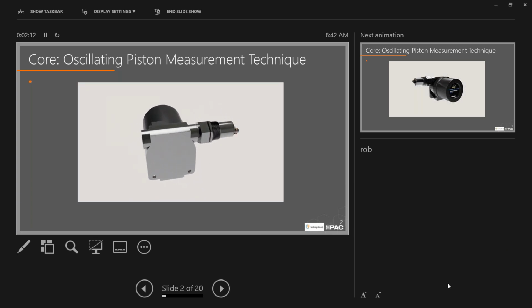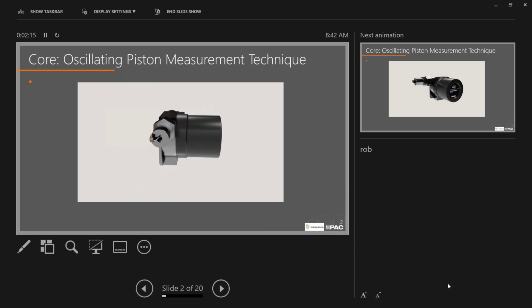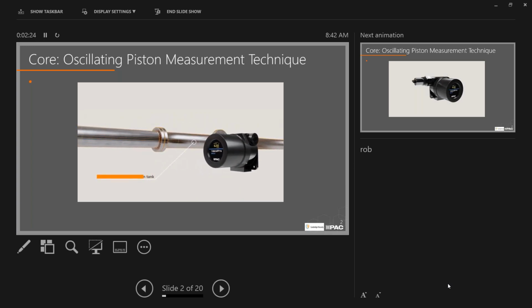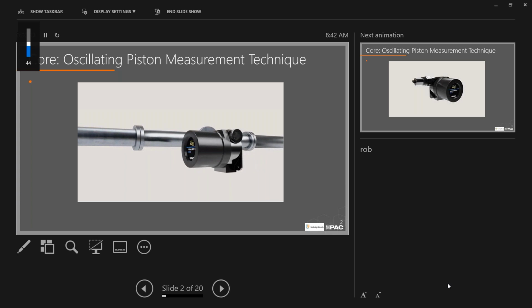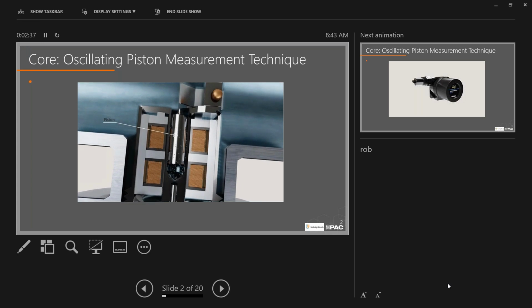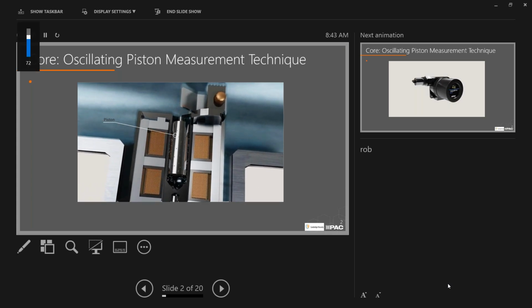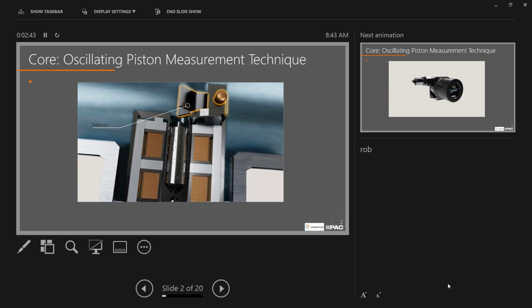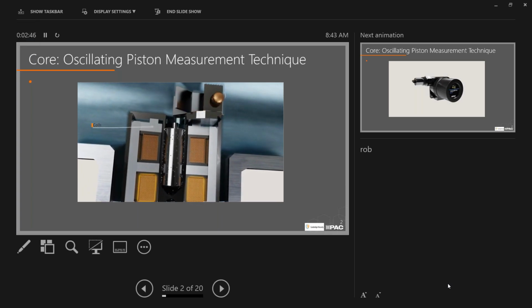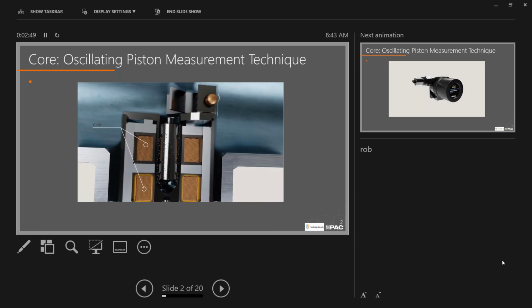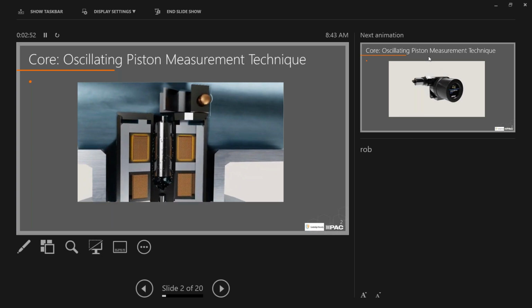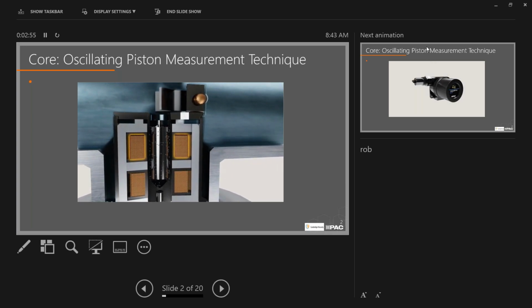At Cambridge Viscosity, our patented sensor technology sets us apart from other viscometer manufacturers, making us the worldwide leader in remote sample viscosity. Our online viscometers install directly into the process, either in-line or in-tank, providing the most up-to-date readings. With only one moving part, a piston is driven electromagnetically through the fluid inside the measurement chamber at a constant force. A deflector positioned over the piston moves fluid into the measurement chamber, while two coils move the piston back and forth. Proprietary circuitry analyzes the piston two-way travel time to measure absolute viscosity.